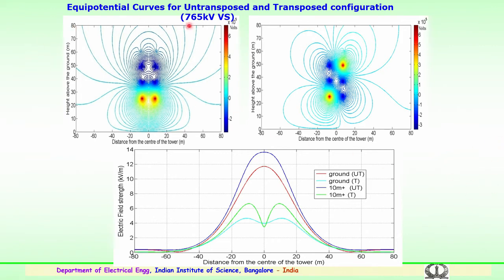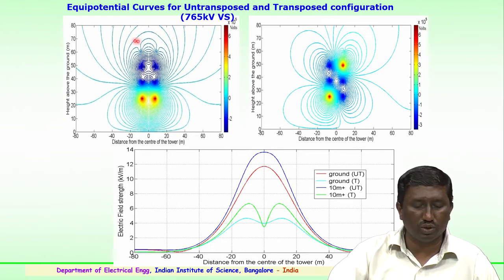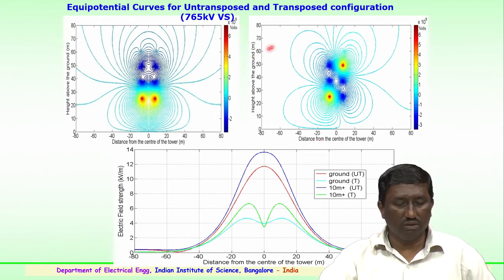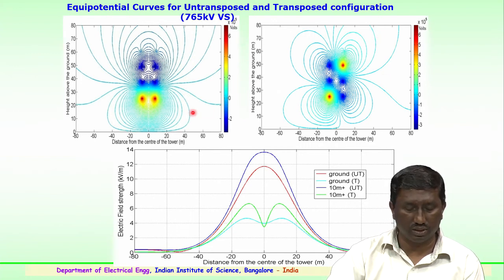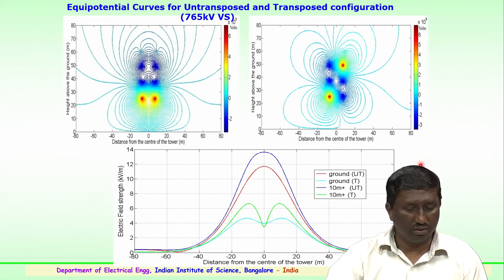So for a 765 kV line, the curves have been shown both for the untransposed, normal tower 765, and for the transposed tower. You can see height above the ground versus the distance from the center of the tower. These are the equipotential plots, which give an indication, and this gives the electric field strength from the center of the tower.